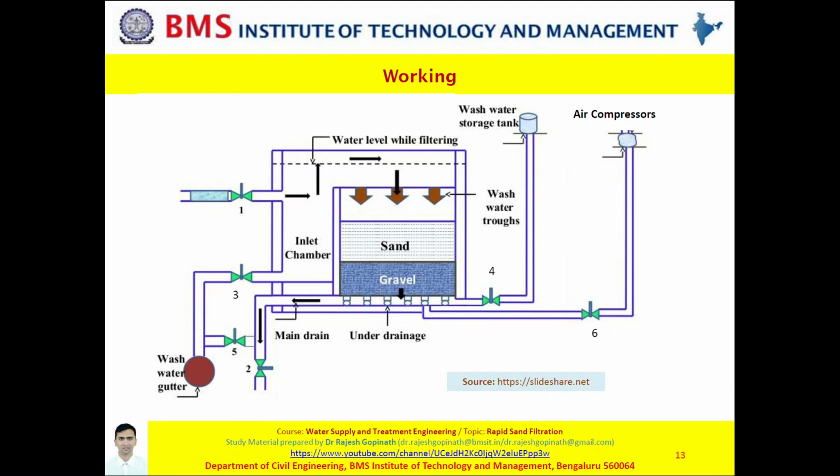After you carry out this operation for a few minutes, you need to now close valve number 5 and open valve number 4, because after a few minutes, the filtration would be back to its normal efficiency. Hence, the filtered water can be collected via valve 4. I hope the explanation is simple and well understood by each one of you.